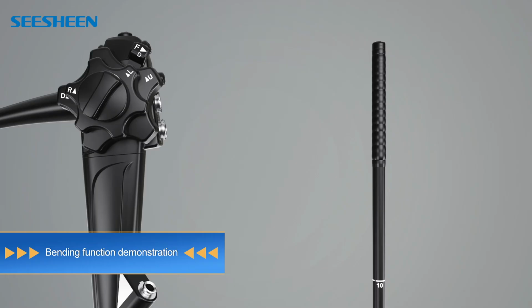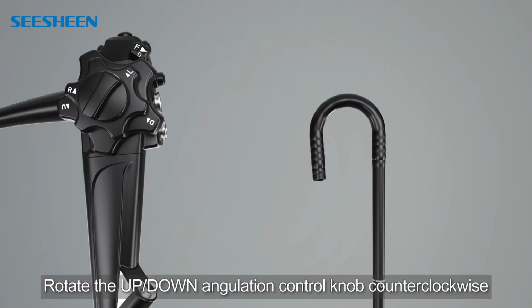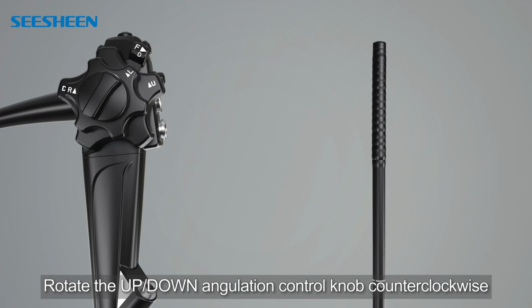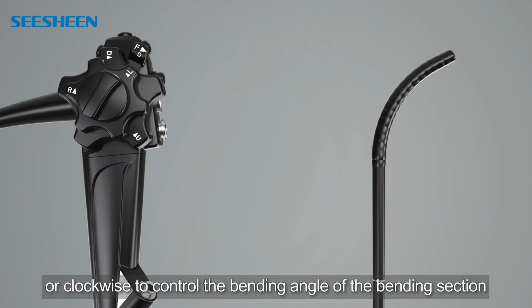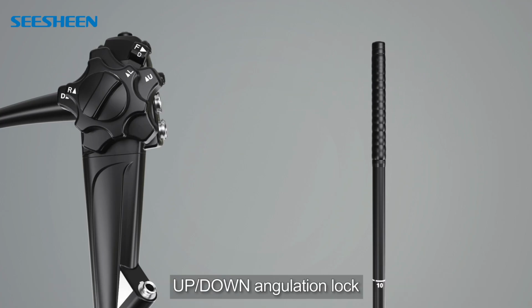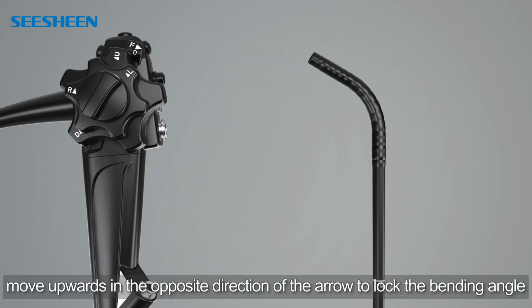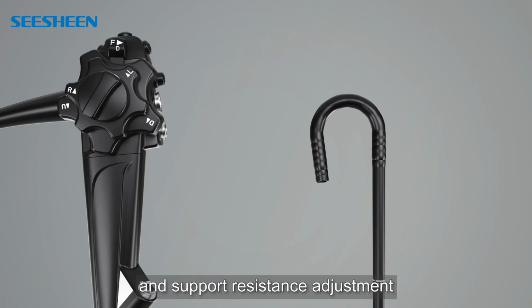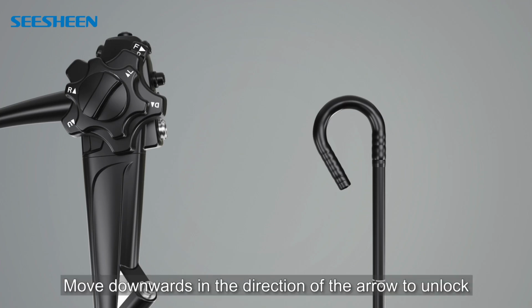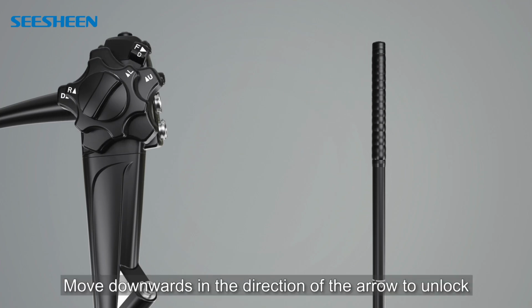Bending function demonstration. Rotate the up/down angulation control knob counterclockwise or clockwise to control the bending angle of the bending section. Up/down angulation lock. Move upwards in the opposite direction of the arrow to lock the bending angle, and support resistance adjustment. Move downwards in the direction of the arrow to unlock.